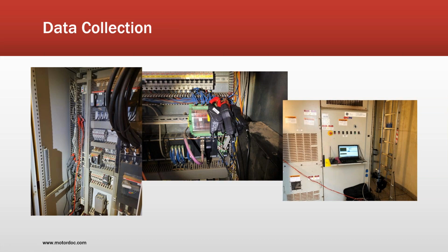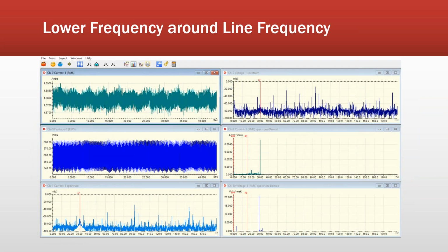There are times when we're on a site and we've said, shut this down, you've got bad wiring and it's serious. And they'll say, well, we'll get to it in a week, and it's gone the next day. So it's pretty accurate. Other times we're seeing 11 to 14 months out. So if we say early fault, it usually means you've got some months to make plans around it.